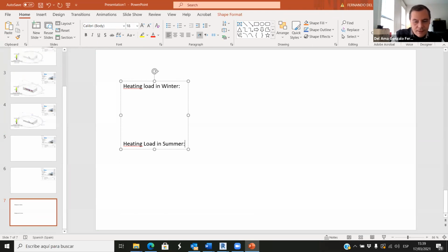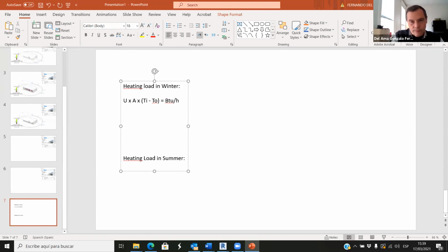And what is this? The heating load in winter is always the U value times the area times indoor minus outdoor temperature. Okay, but what are the units of this? This is BTU hour. This is the heating load.